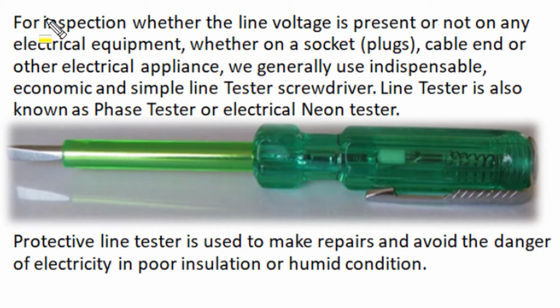To inspect whether the supply line voltage is present on any electrical equipment or electric wiring network, whether it is a socket outlet, a plug point, or an end terminal of a cable or wire, or in fault finding of any electric appliance or circuit, we generally use an indispensable, very economic and simple tool, the line tester screwdriver. This line tester is also known as a phase tester or neon tester.